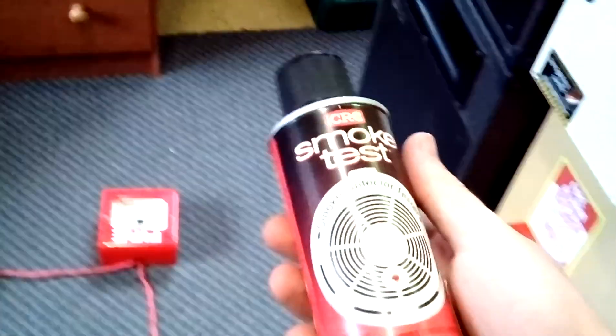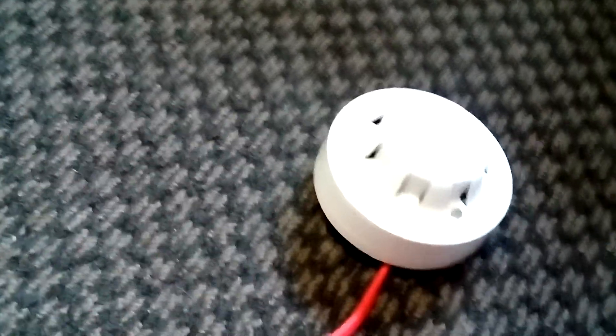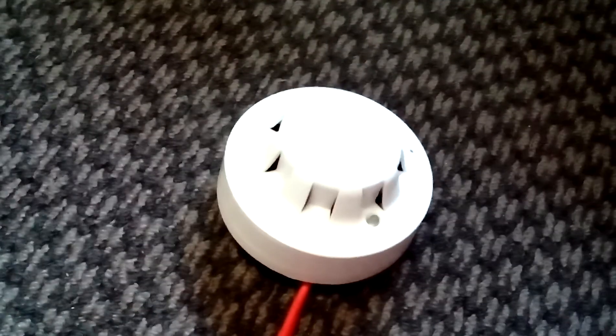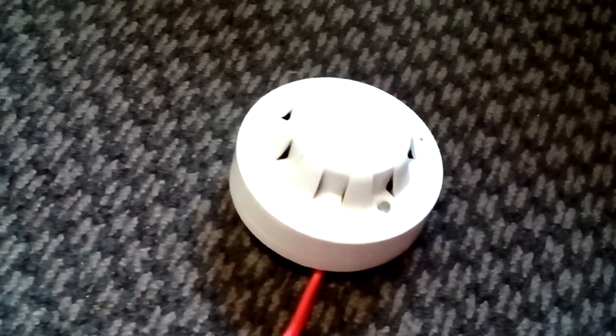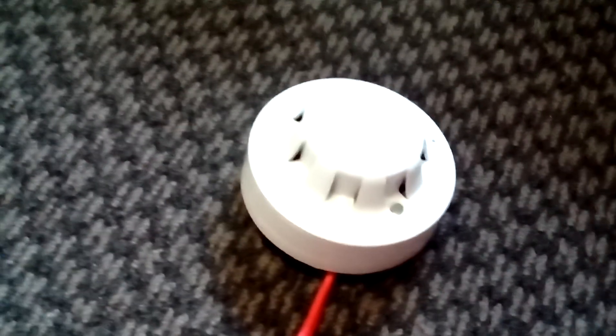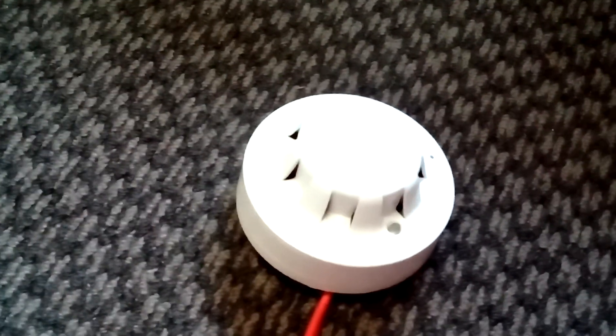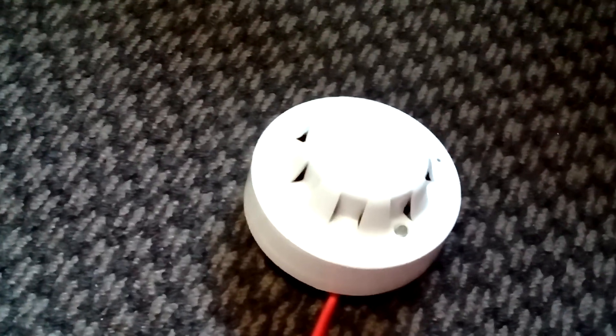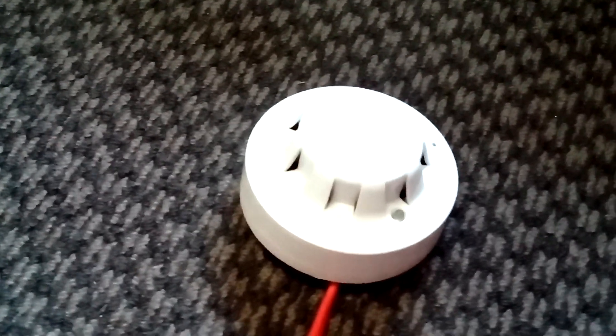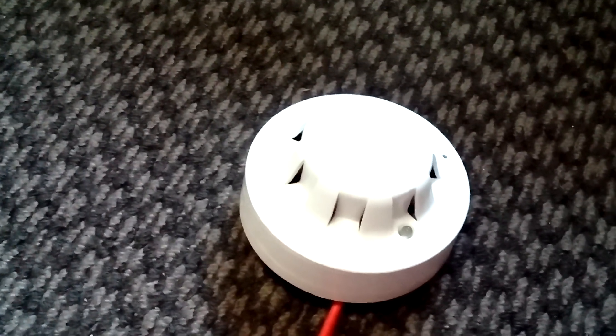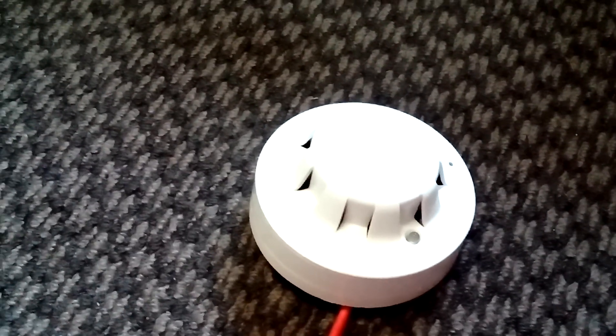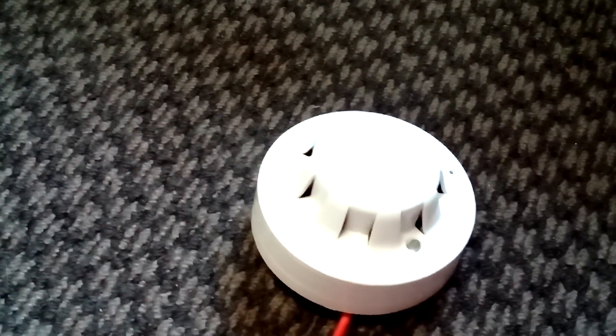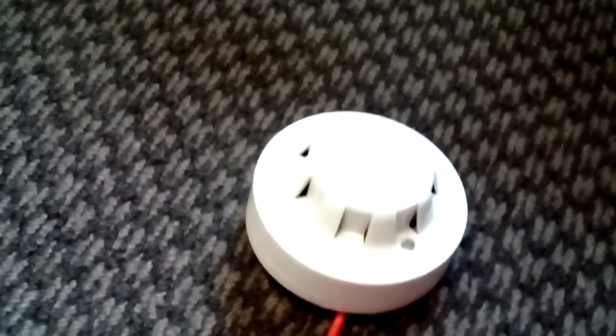Now we'll try the smoke detector but I will take it off walk test mode. I got my trusty can of smoke here. I don't like using too much of this stuff but unfortunately with these GameWell smokes it's the only way to set them off, they don't have a reed switch in them. There we go, that's the false alarm prevention. So we'll wait about 30 seconds and then we'll spray it again. These are quite sensitive actually, I probably won't need to spray anymore, it should just go off in a few seconds. Might need a tiny bit more.